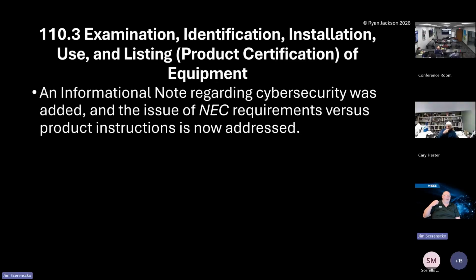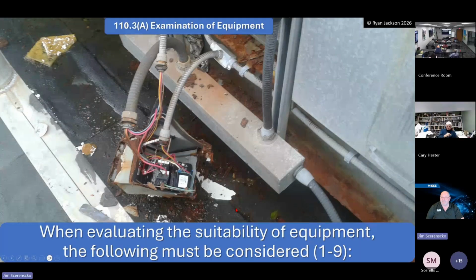If somebody hacks into my system, and we have a breaker that's an adjustable trip set at 2,000 amps, and somebody goes in there and jacks it up to 4,000, all of a sudden it starts overloading without tripping, and we blow up some building. There's that possibility. So cybersecurity has become a big deal because there's so much advancement in the way breakers are controlled.